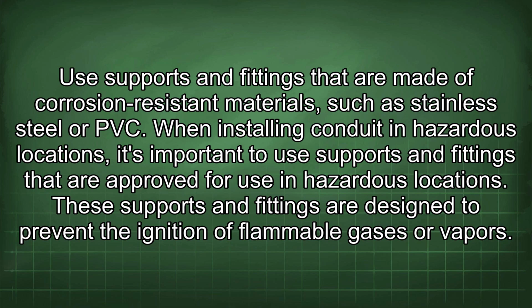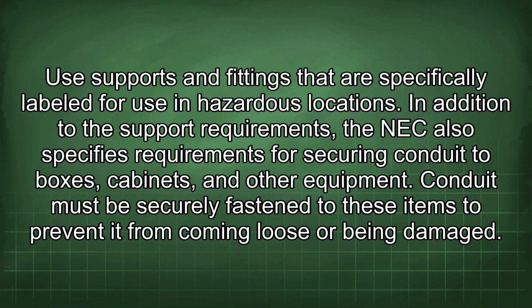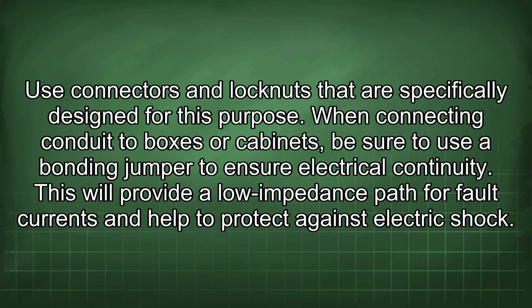When installing conduit in hazardous locations, it's important to use supports and fittings that are approved for use in hazardous locations. These supports and fittings are designed to prevent the ignition of flammable gases or vapors. Use supports and fittings that are specifically labeled for use in hazardous locations. In addition to the support requirements, the NEC also specifies requirements for securing conduit to boxes, cabinets, and other equipment. Conduit must be securely fastened to these items to prevent it from coming loose or being damaged. Use connectors and locknuts that are specifically designed for this purpose.